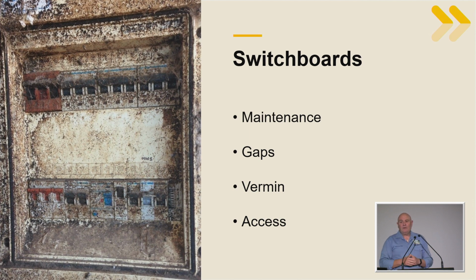Safety switches and circuit breakers are exactly the same - you need to operate them every now and then. Our office recommends testing all your safety switches every three months. When testing the safety switches, turn your circuit breakers off, then turn them back on again. They're a mechanical device, electromechanical, and they do need to be operated.